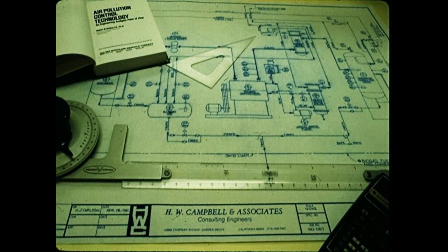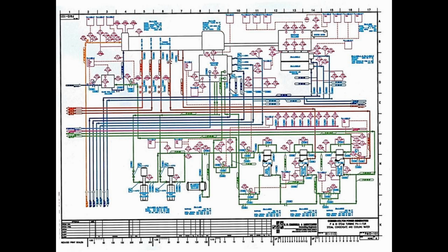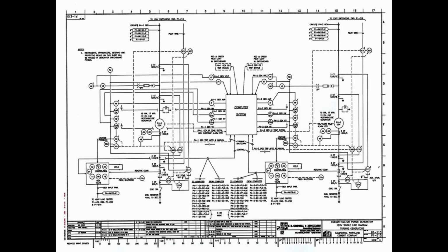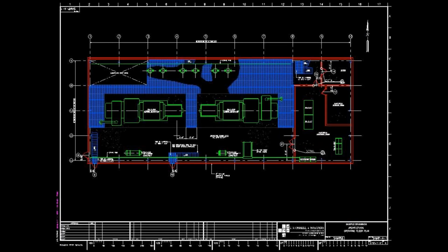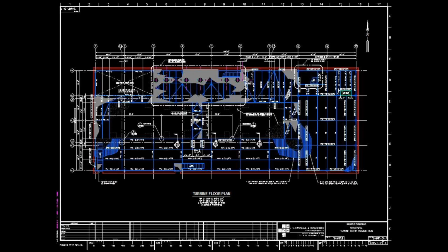The cogeneration and coal-fired boiler facilities were integrated into the existing plant, which remained operational throughout construction. It was extremely critical that planning of the installation be precise. Over 900 drawings were required for construction of the project, and approximately 50 detailed purchase specifications were prepared for equipment and material. A design to permit the sequenced construction of a waste heat boiler and bypass ducting enabled cement kiln outage to be limited to 4 weeks. Planning for the shutdown phase of the project included prefabrication of all large ductwork and refractory lining of cyclone separators prior to shutdown.